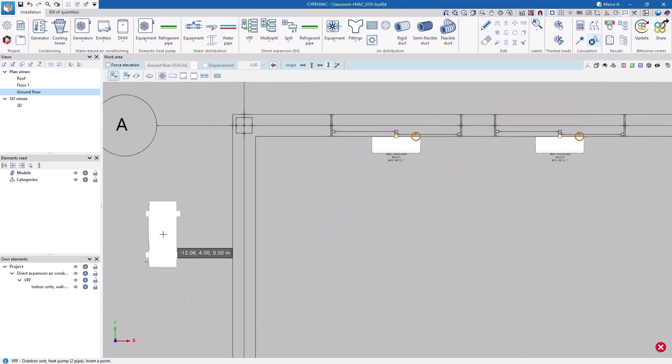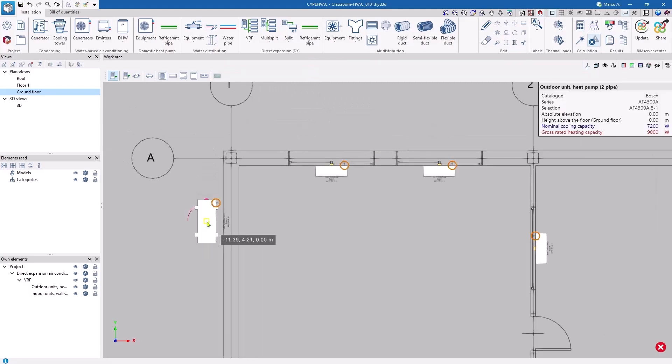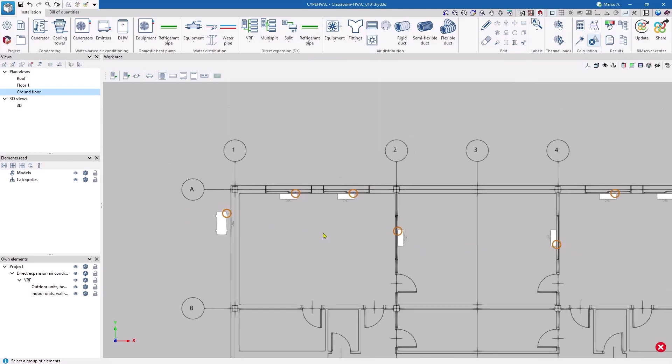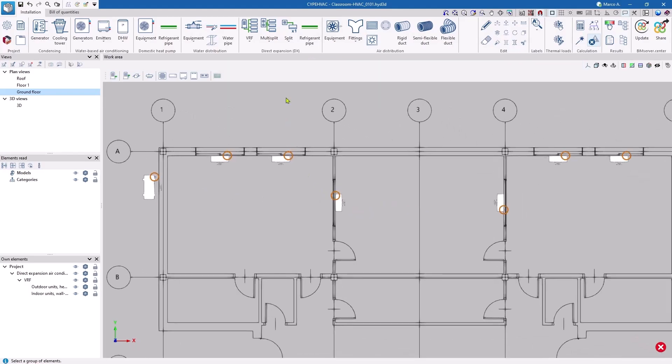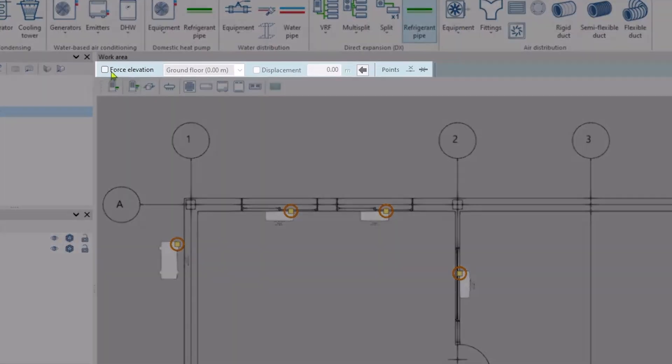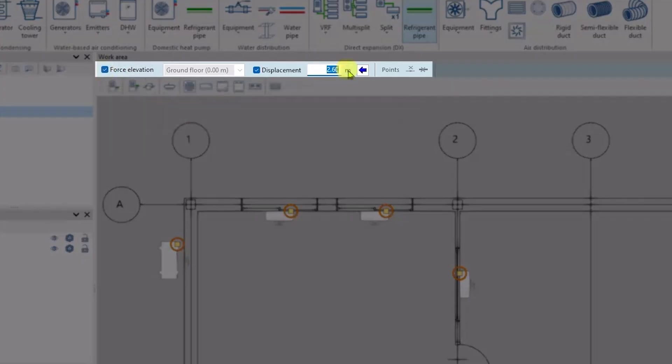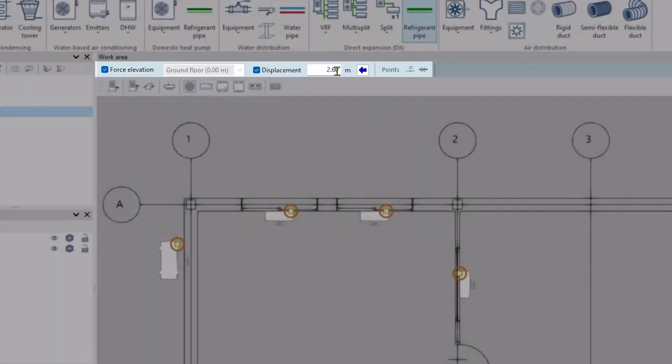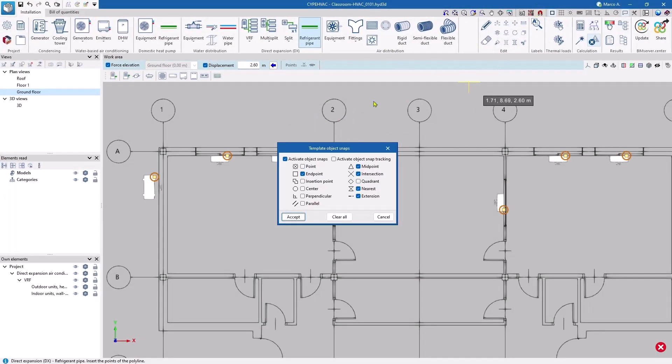Again, once the series has been chosen, the program selects the appropriate model according to the overall thermal requirements. We connect the units with the refrigerant pipe layout. In this case, we will assign a displacement above the reference level. If we have a suspended ceiling at an elevation of 2.50, we can define a height of 2.60 for this layout.